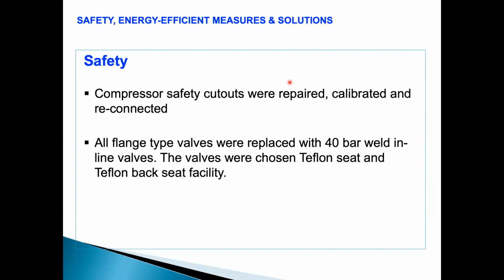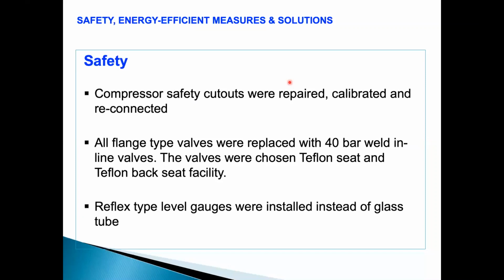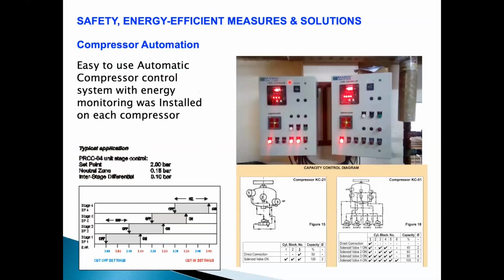All flange type valves were replaced with high pressure 40 bar welded line valves with back seating and Teflon seat arrangements. Reflex type level gauges were used instead of glass tubes, which avoids the breaking of tubes and leakage of ammonia, and also gives a correct indication. Compressor automation was implemented for each individual compressor. Each compressor was made automatic independently. So depending on the requirement, the operator can decide which compressor he wants to run, start the compressor and let it work automatically. Those are piston compressors, so they were operating manually.